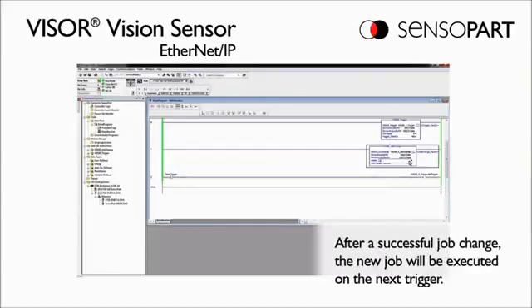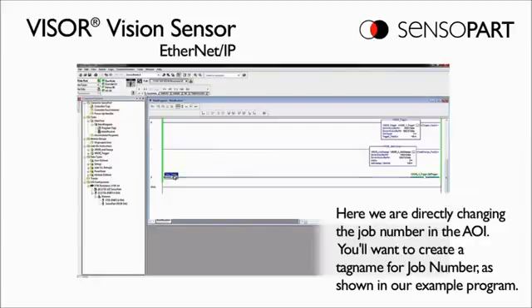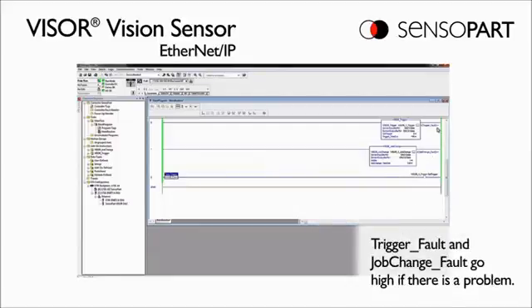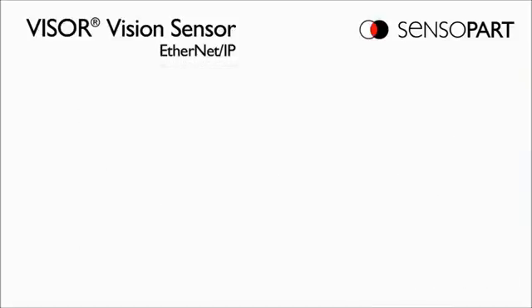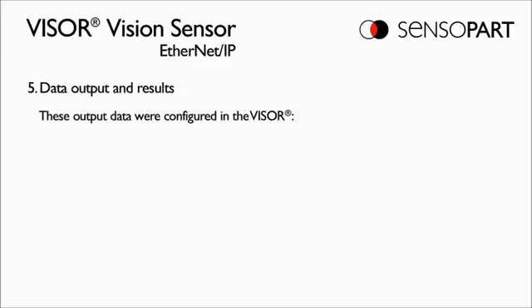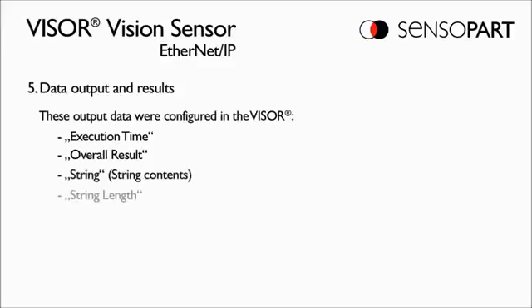After a successful job change with no errors, the VISOR is ready to run the new job. On the rising edge of the next trigger, it'll run the newly selected job. Obviously, you'll want to add a tag name for the job number. Next, we're going to test communications by looking at the camera configuration software to see what some values are and monitoring the input buffer in the PLC to verify those same values got transferred across.